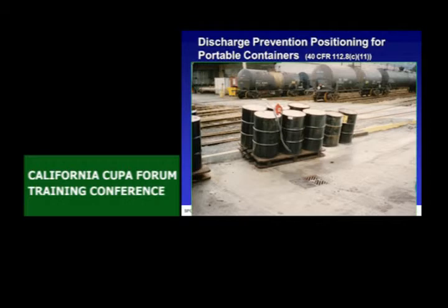Yes, good. That's a good point. If these were being operationally attended, and the drain wasn't there, general containment is sufficient for containers in attendance. But that guy goes to lunch, guess what? If it goes out to the stormwater, navigable water, if that goes to a separator, that's fine. Problem is you can't really tell by looking at it. And this, actually, goes out to a harbor.